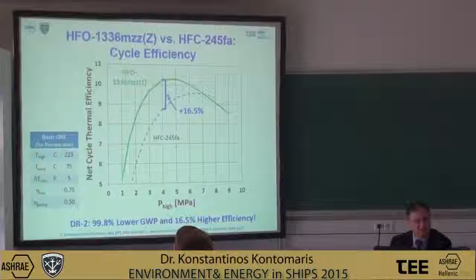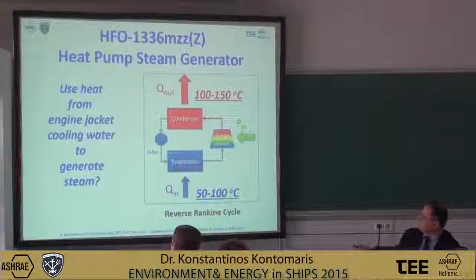One could use low temperature heat. On some ships there is need for steam generation, and now high temperature heat is used to accomplish that heat generation. Of course, high temperature heat is valuable, and I would rather use it to generate power. But then I would need an alternative way to generate steam, which means I need to heat water at temperatures higher than 100 degrees. And that can be accomplished again with a heat pump using this new fluid by providing colder temperature heat to the heat pump, and the heat pump then lifts that temperature to a level where steam can be generated.